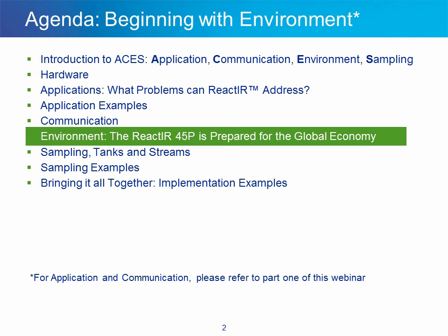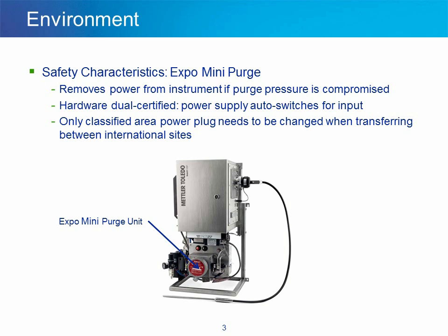The ReactIR 45P is prepared for the global economy. The Expo Mini Purge automatically removes power from the instrument if purge pressure is compromised. There is no conversion between North American and European requirements. The hardware is dual certified. The power supply auto-switches for input — for example, U.S. 110 volts, Europe 240 volts — so that the ReactIR 45P is global ready. Only the classified area power plug needs to be changed when transferring the system between international sites.